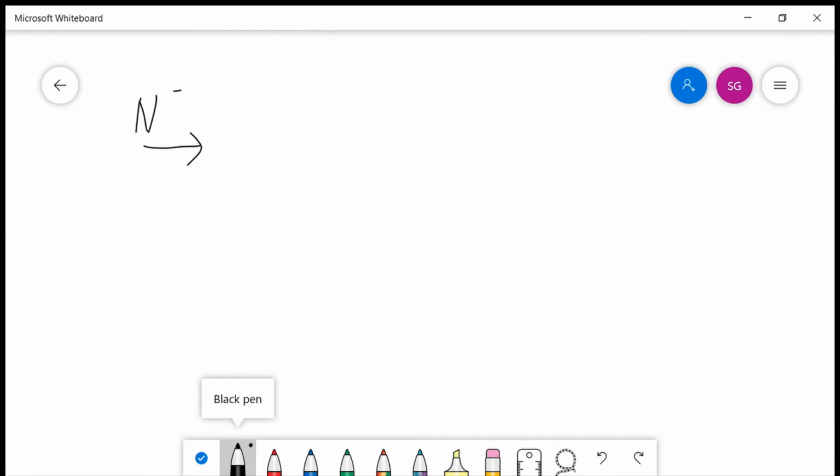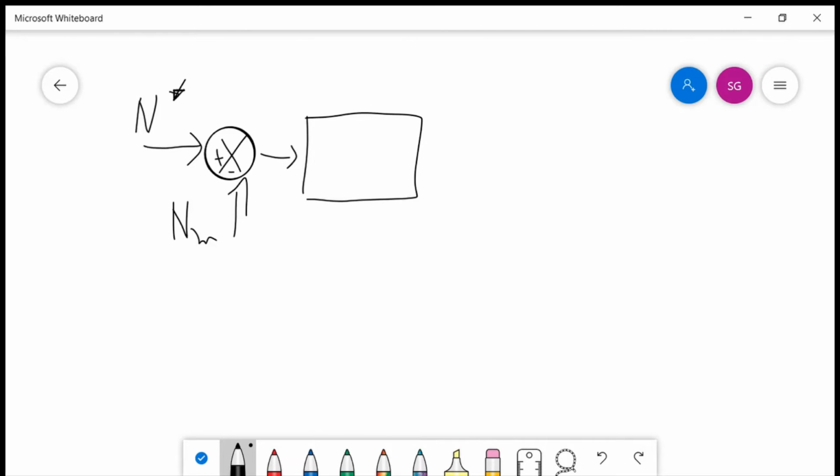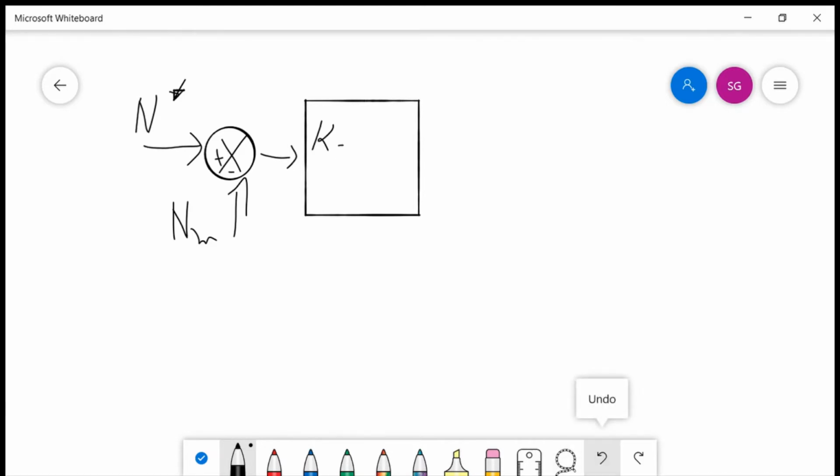So here is your reference signal, which is compared to your measured signal, the measured speed. This will be passed to a PI controller, a speed controller. Let us write it as KS, because this is a speed controller, so it will be KS (1 plus TS s) over TS s. TS is the time constant of this speed controller. This will give you IA star, the IA reference signal.